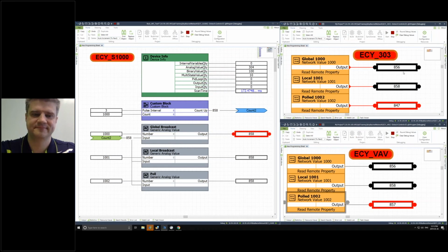The reason I wanted to mention that is this goes back to something similar to a client-server relationship, where it's not the same, but the concept is the same. We made a change in one location, and now everybody benefits from that change. If we're polling a device peer-to-peer, and I have 600 controllers polling, say, an air handler, then if I want to make a change, I have to go into each one of those controllers and adjust how they poll, right? Because it's just going peer-to-peer. With a broadcast, one controller is sending out information to everybody else. In a sense, it's acting like a server for that information. It's almost an analogy, but it works for this case to showcase the difference between client-server and peer-to-peer. Although you could make the argument that it's still peer-to-peer, but you have to forgive me for this one.